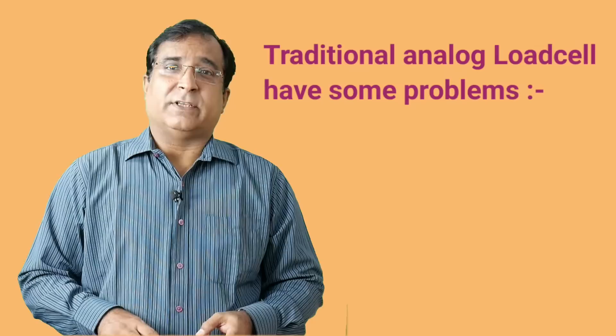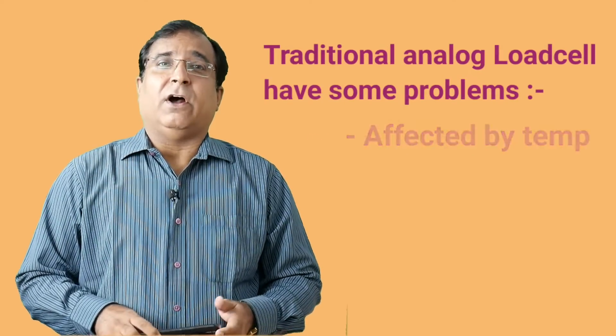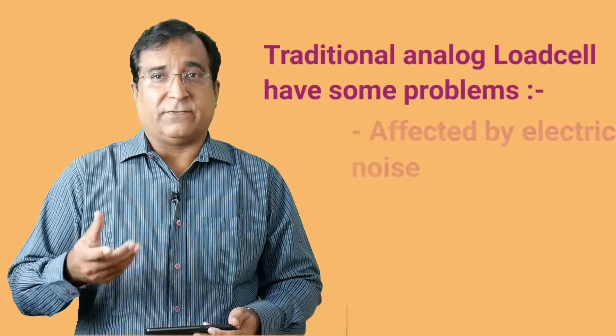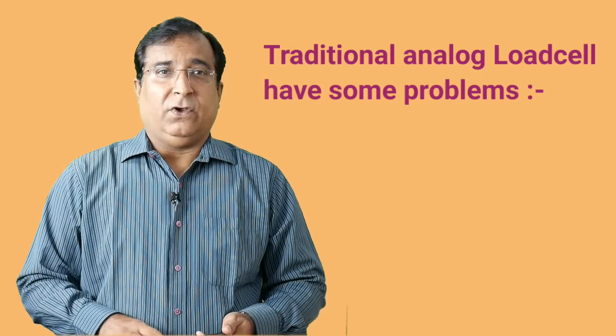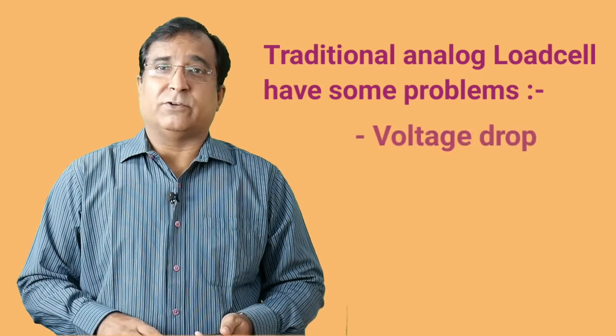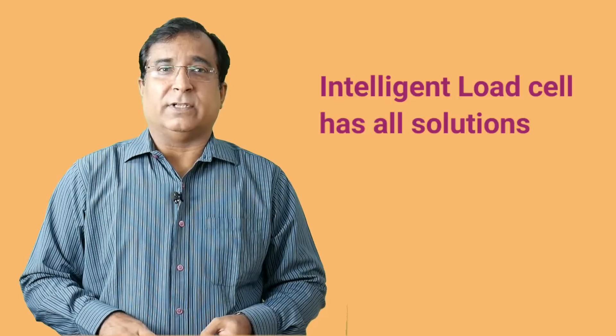In the latest development, intelligent digital load cell is replacing older generation load cell. The analog load cell has some issues like signal is affected by ambient temperature variation. Also electrical noise or interference causes false millivolt to superimpose on the cable line. It may corrupt the reading. A 4 wire load cell has inherent voltage drop over cable line. Due to these reasons signal accuracy gets compromised. All these issues have been addressed in intelligent load cell.